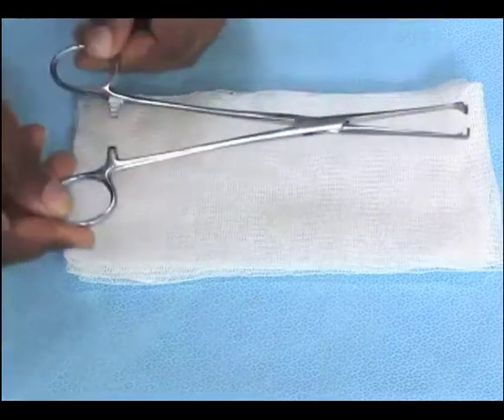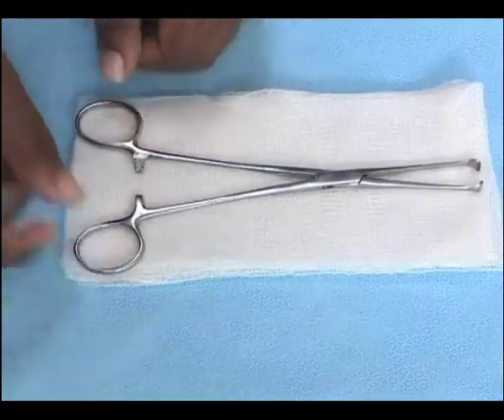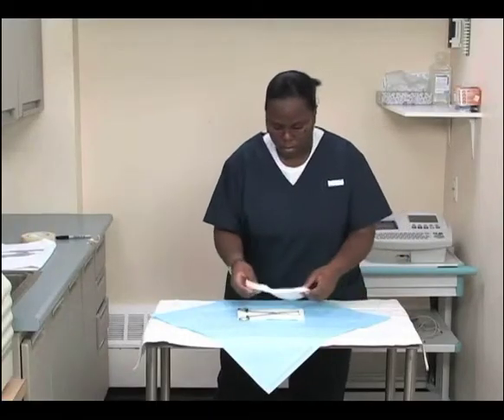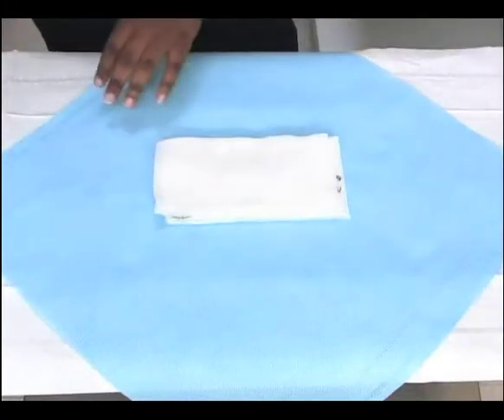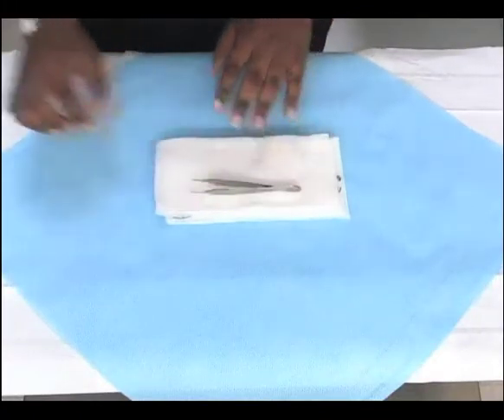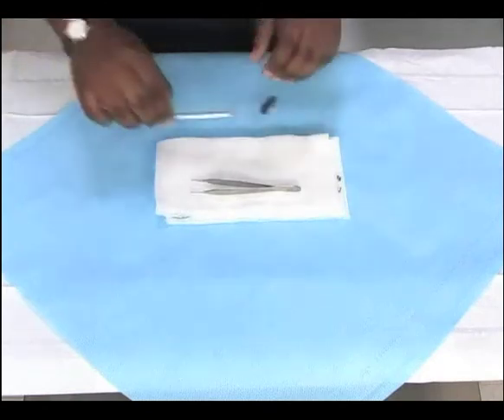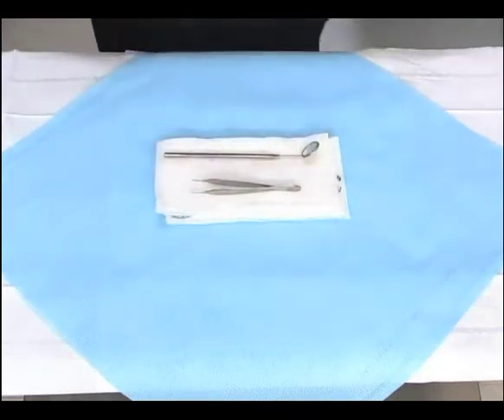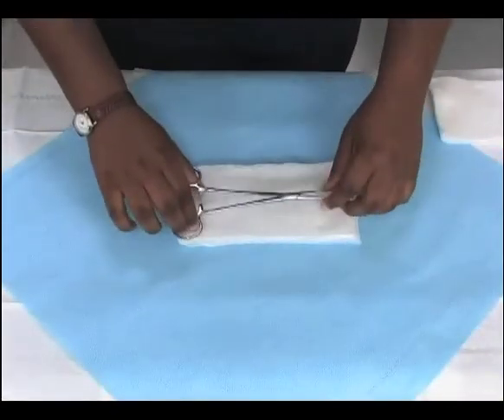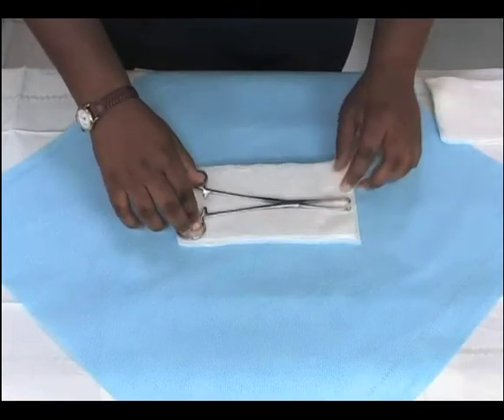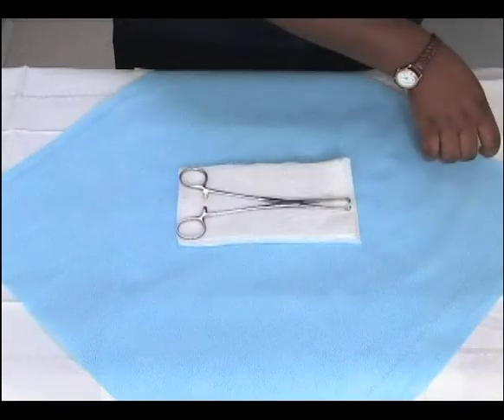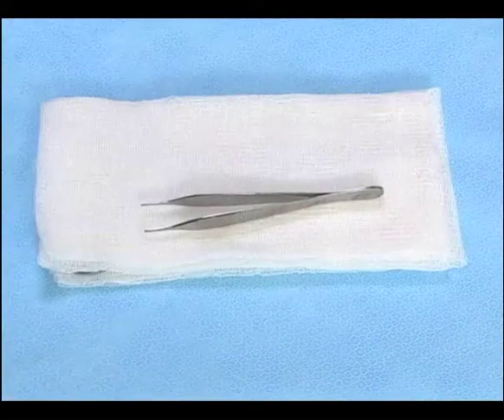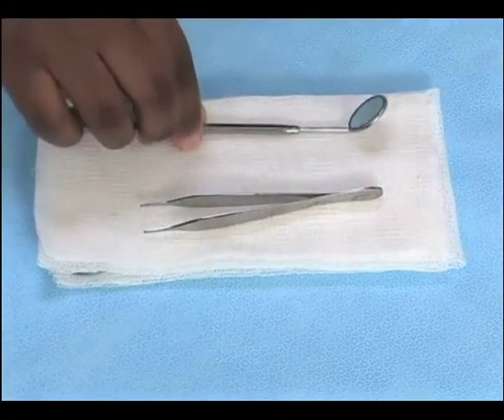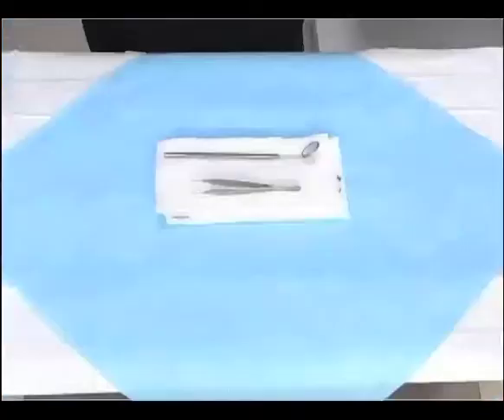Begin by placing instruments in the center of the wrapping material. Alternate instruments with any dressing materials that may be required for the procedure. Whenever possible, sterilize items in small packs so that the steam can penetrate more easily. Hinged instruments should be slightly open to allow steam to penetrate and sterilize the hinge area. Position instruments in such a way as to prevent metal-to-metal contact within the pack.